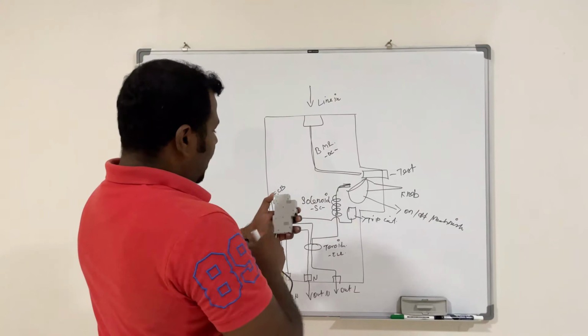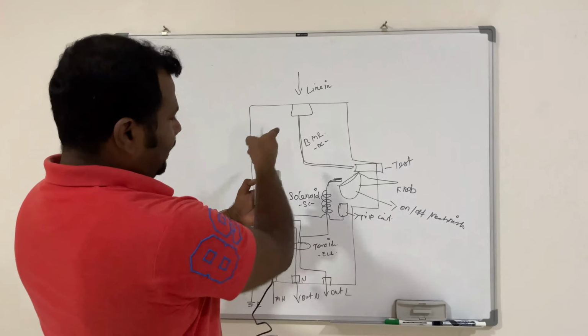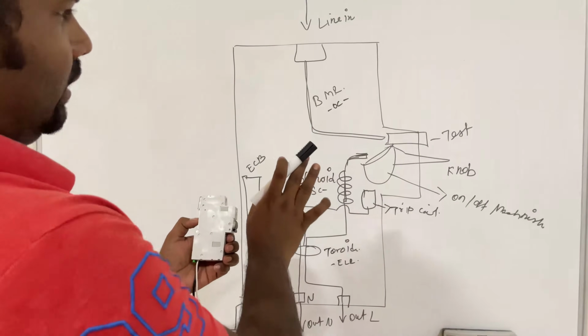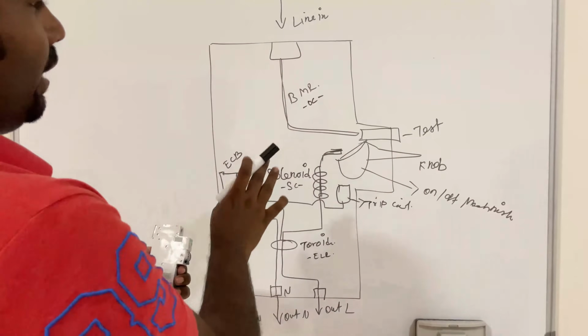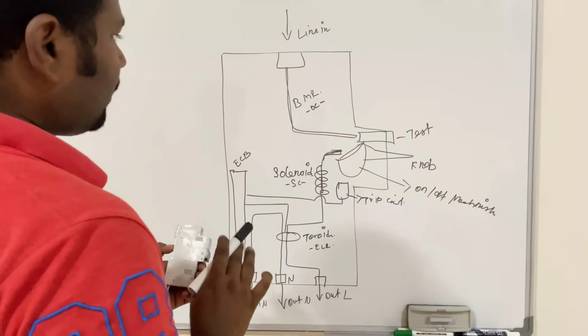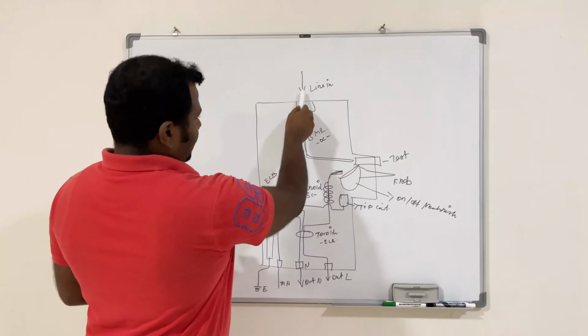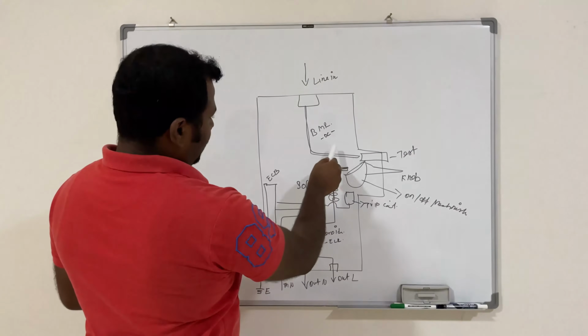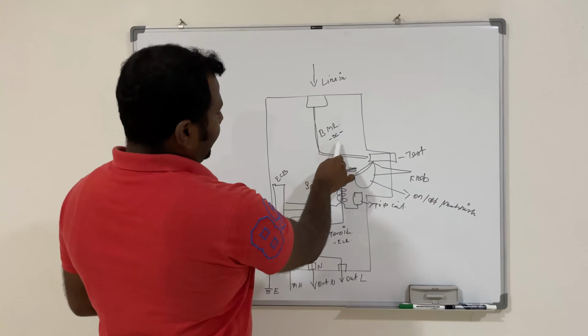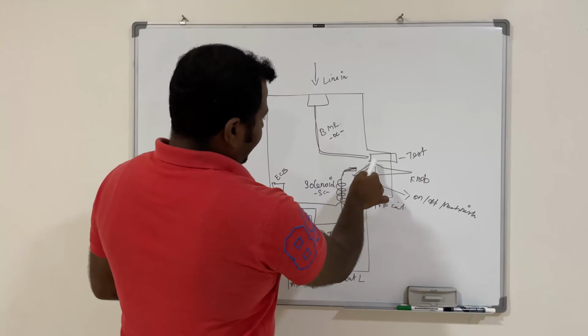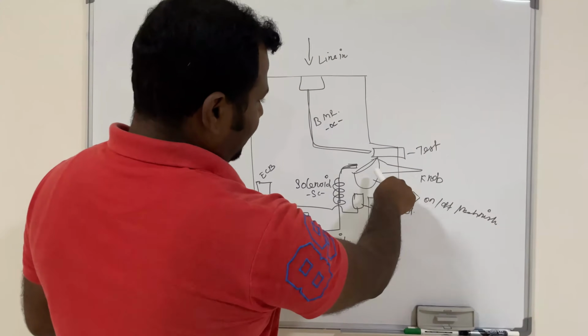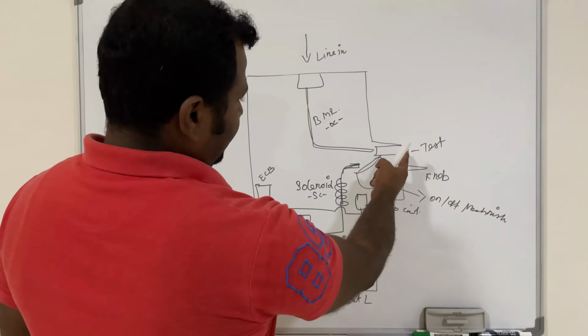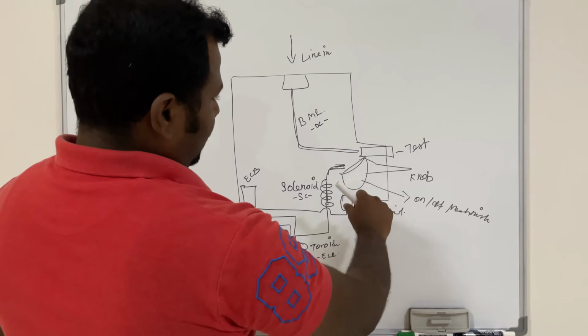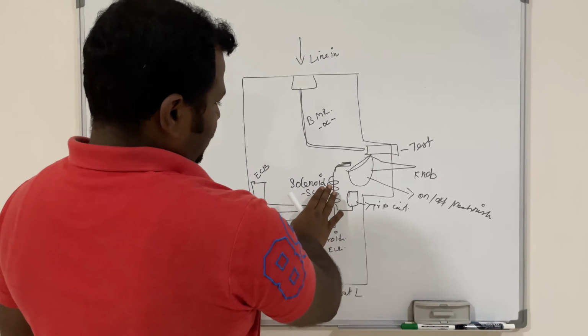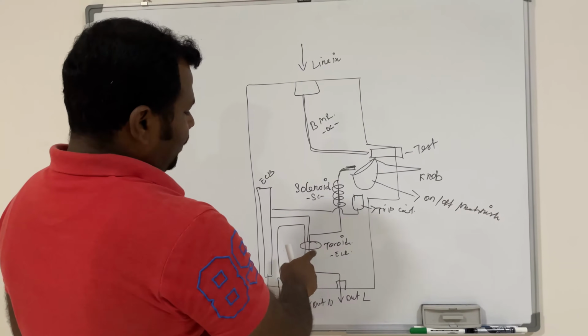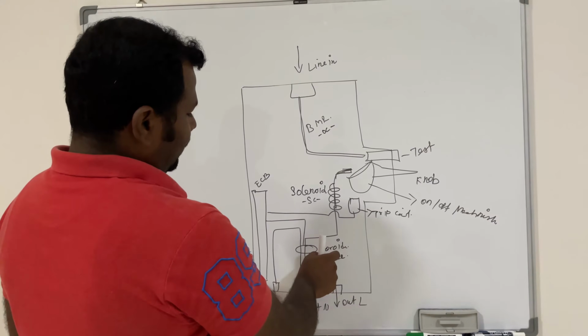So this is the internal view of the RCBO. Once you open this cover, it will look like this. Internally we will see what accessories are there, how it is working, and what it protects us from. This is the main incoming, feeding through the BMR, the bimetallic strip, which will take care of overcurrent protection. There are knobs for on off purpose and a test position, as I told you, a test switch. There is also the on off mechanism, which is connected with the tripping mechanism. And there is a toroid CT which will measure the imbalance current for earth leakage protection.